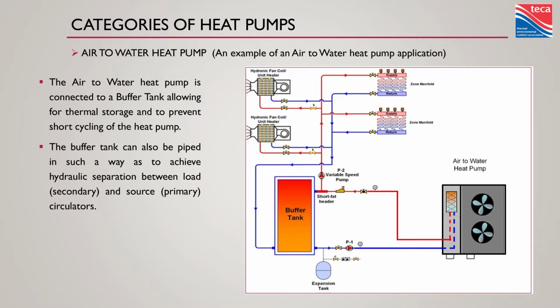Buffer tanks. Buffer tanks are another key ingredient in a successful hydronic heat pump application. When we're dealing with a forced air heating system, we probably aren't zoning it very much. And if we are, it's maybe 2, 3, 4 zones max if it's a central ducted system, so maybe a quarter of the total load. I've seen houses with 60 hydronic zones in them. It's insane. We're dealing with tiny micro loads. The other problem here is the heat pump is so effective when the temperature is mild that there is so much heat energy it's generating when there's almost no load. We are going to short cycle that thing without a way of storing thermal energy.